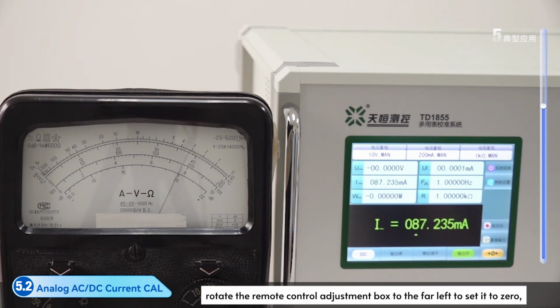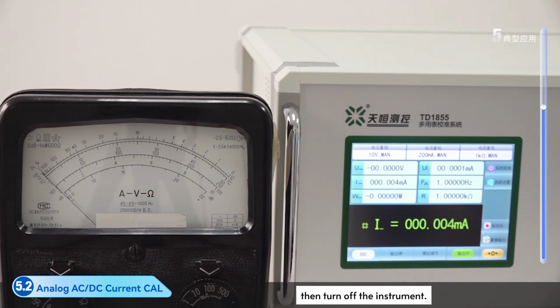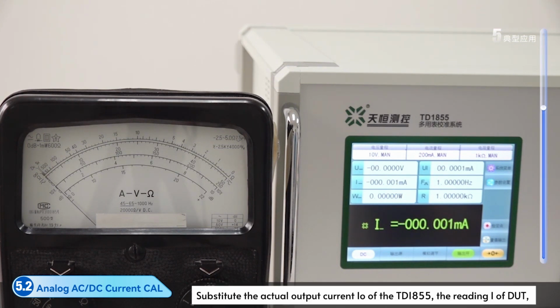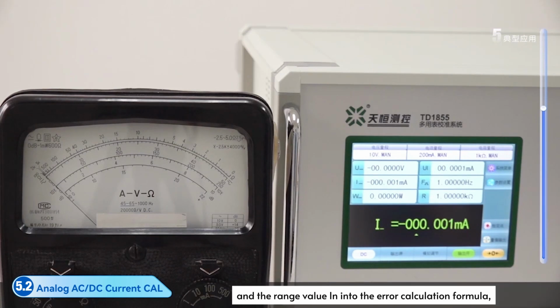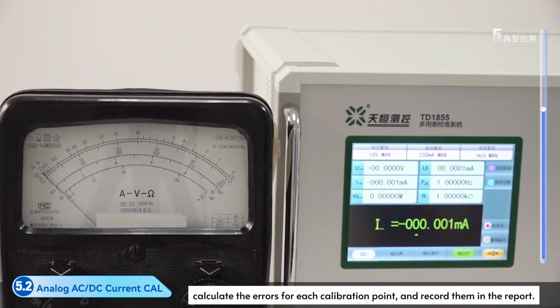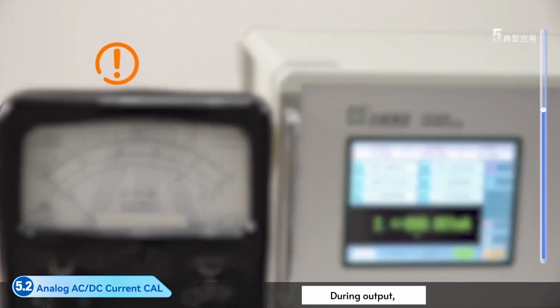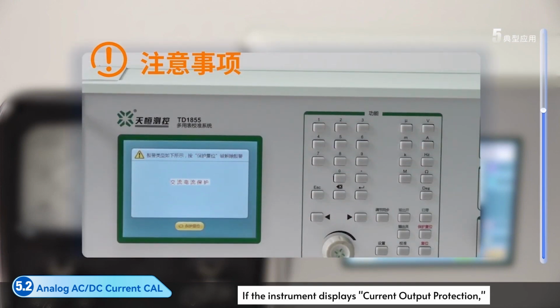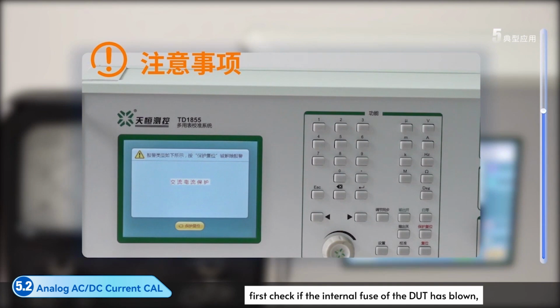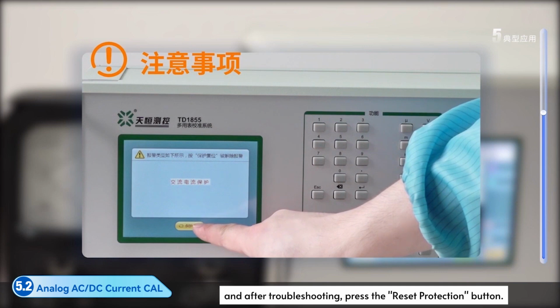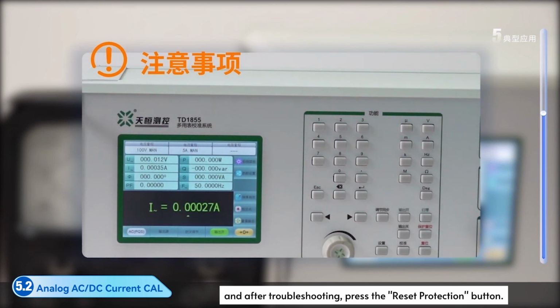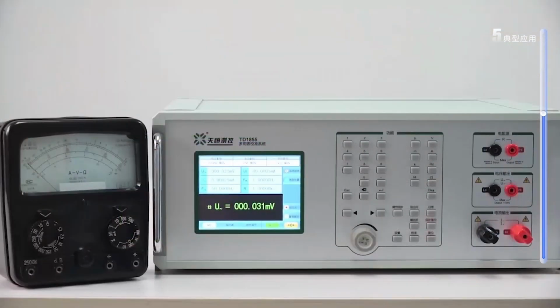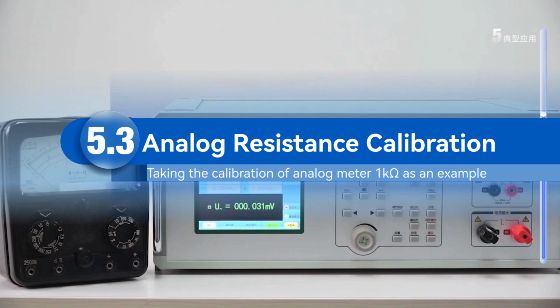After testing, rotate the box knobs to the far left to set it to 0, then turn off the instrument. Substitute the actual output current, the reading of DUT, and the range into the error calculation formula. Calculate the errors for each calibration point, and record. During output, if the instrument displays current output protection, first check if the fuse has blown. Then check if the output terminal wiring is correct, and check if the load is too large or damaged. And after troubleshooting, press the Reset Protection button. Part 3. Analog Resistance Calibration.